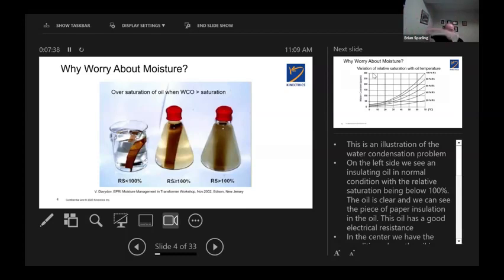It's relative humidity. So water in an oil, water in another fluid, that's talked about in terms of relative saturation. In the middle is a beaker of oil that has reached saturation, where the relative saturation is at or just over 100%, and it looks cloudy, foggy, just as air would be when it reaches 100% humidity. On the right-hand side, you'll see where the oil has now become supersaturated with moisture, and in the bottom of that beaker can be found free water. In other words, inside that beaker, the water has condensed in the oil and fallen to the bottom, and it basically has rained inside that beaker.